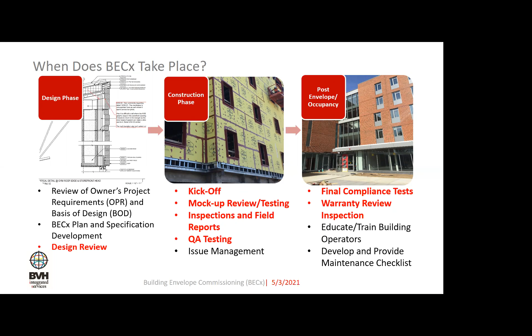Yes, that's a great point. For instance, in Vermont, there are two paths to compliance with this air barrier commissioning. You can either have construction phase commissioning take place, or you can say we're not going to commission, but we're going to meet a blower door test requirement, which is a quantifiable test.